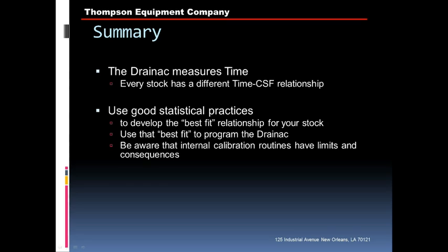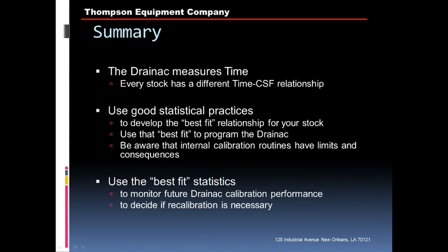There are some built-in internal calibration routines. They all have limits and consequences. You need to be aware of that. Use the statistics that are derived from your best fit regressions to monitor the performance of the Drainac and make a decision as to whether or not recalibration is necessary as you go forward in time.